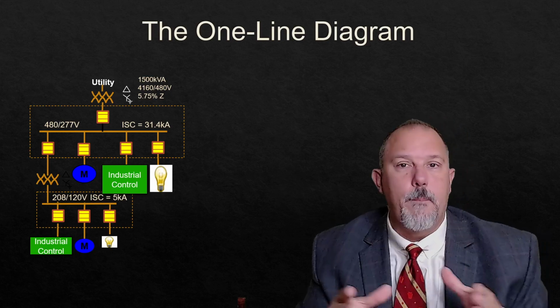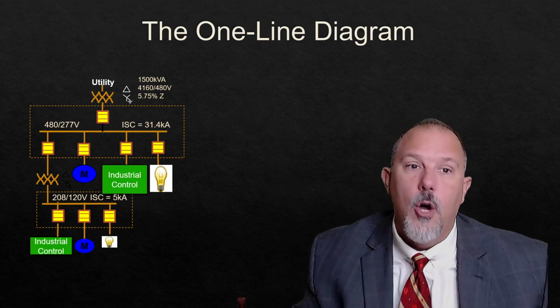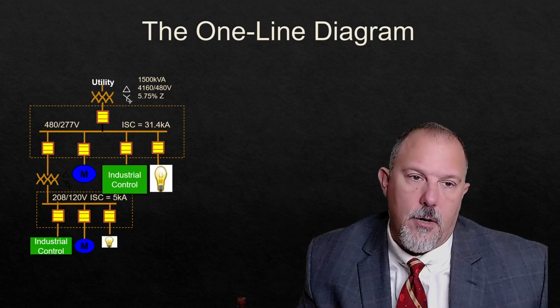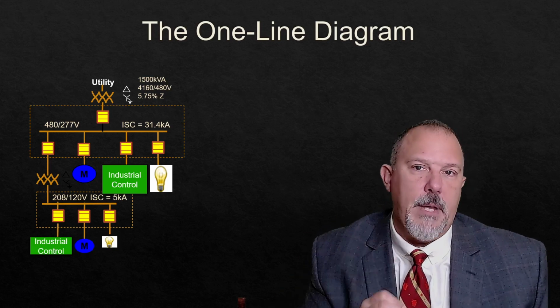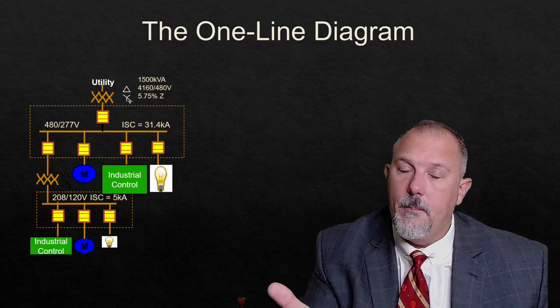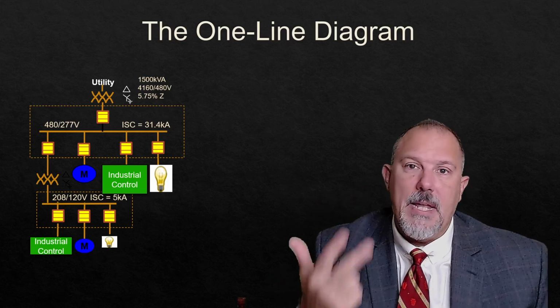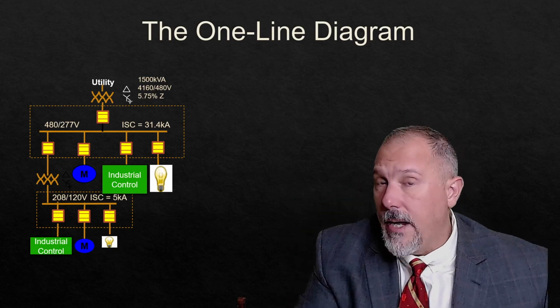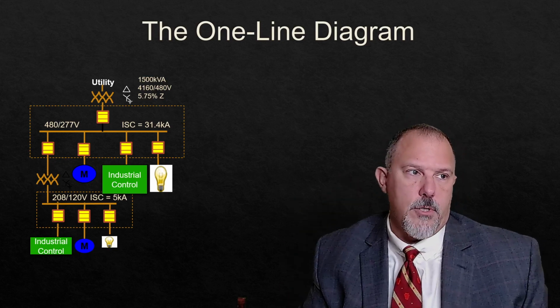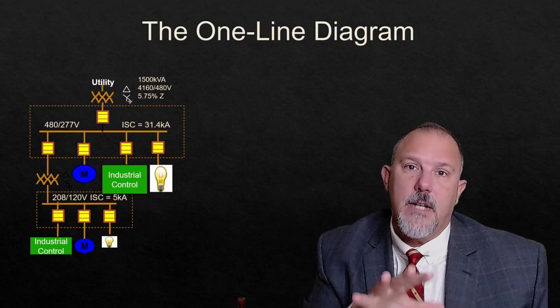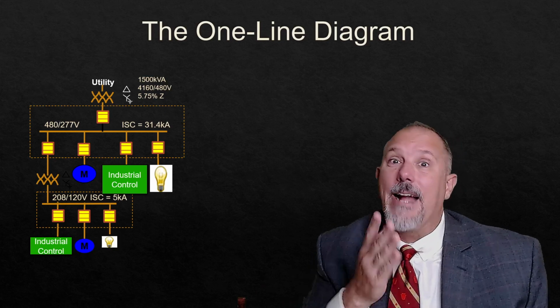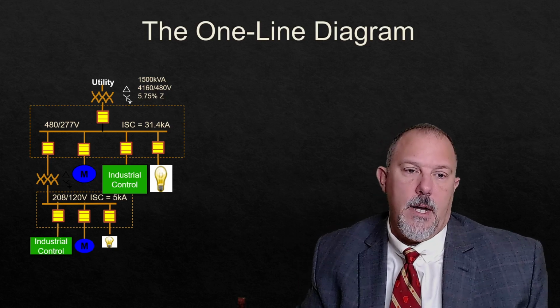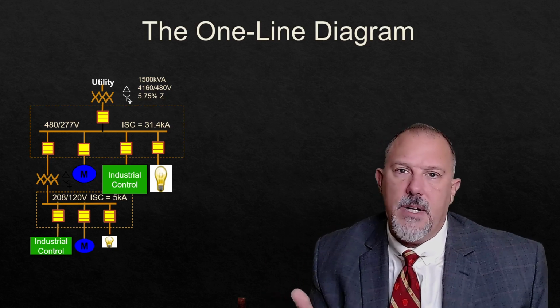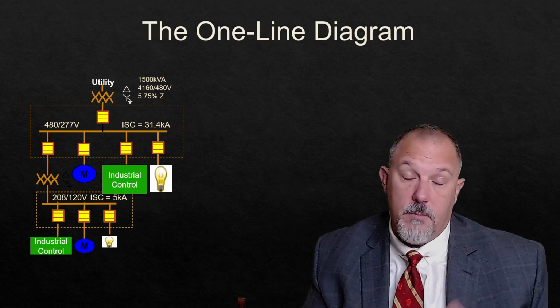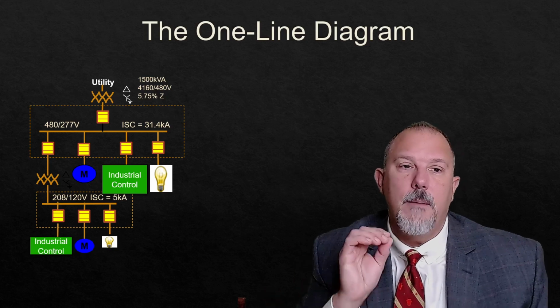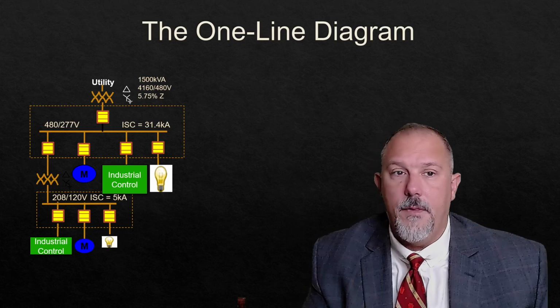Now, we don't consider impedance of bus like it's in a panel board or the impedance of a fuse or a circuit breaker. We look at the big components of impedance: transformer impedances, conductor impedances, busway impedances, motor impedances, generator impedances. What else? Inductors, if you have an inductor in there. Line reactors is what I mean, a line reactor. We don't model the impedance of bus inside of a panel board or switchboard. The big copper, we don't need to do that. The impedance is insignificant on the overall picture.